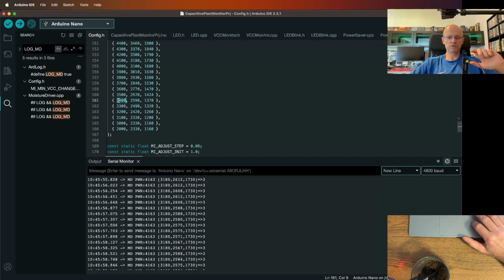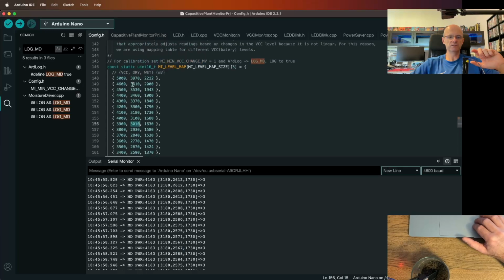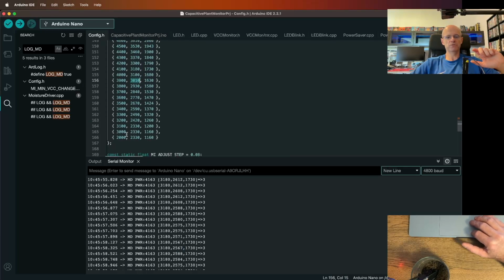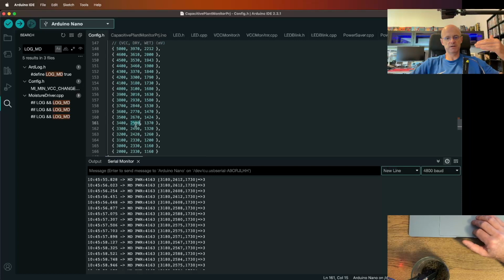Increase the voltage to 3.4 volts, take the reading in the middle and put it here. Go on and on up to 3.9 volts, copying the value from the middle each time, and so on. So you want to stick the sensor into the dry soil and go over each possible voltage level, putting the sensor reading into that column, which is the dry level.